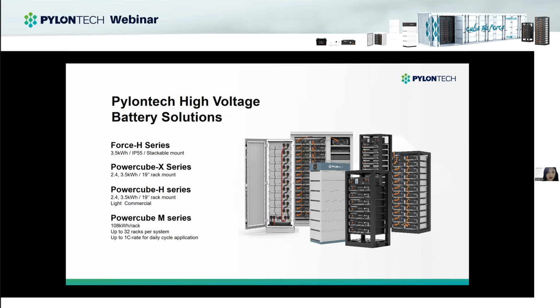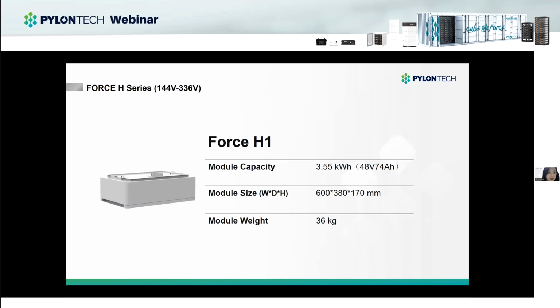Our company has many high voltage battery solutions like the Force H series, Power Cube, X, H, and M series. And today I will focus on the Force H series for residential use. The single battery module is 48 volts and 74 amp hours, and the module capacity is 3.55 kilowatt hours. The module size is 600 millimeters width, 380 millimeters depth, and 170 millimeters height. The single battery module's weight is 36 kilograms.